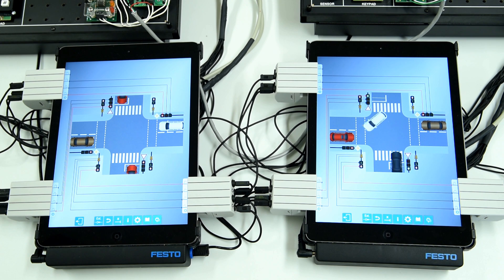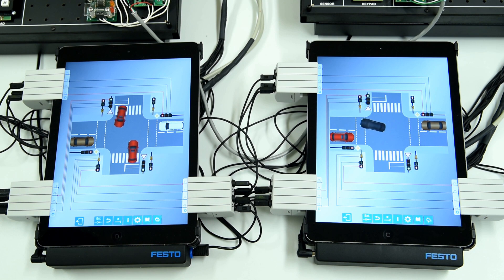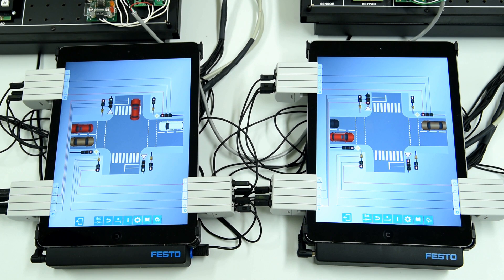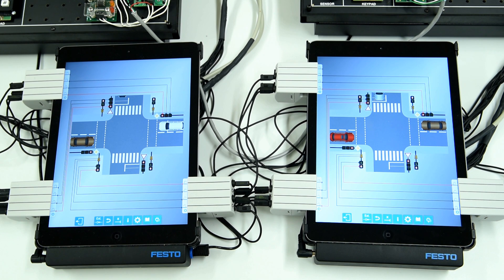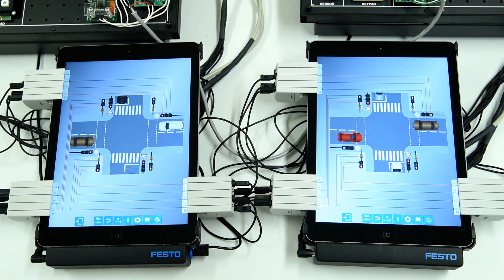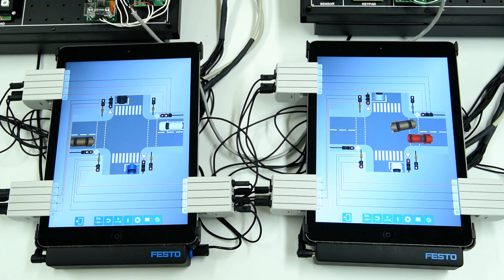And a pedestrian time message is exchanged between the controllers. Once both controller data bytes are set to ON, the pedestrians of both intersections get the light to cross. After a delay, the sequences are resumed, the data is reset, and traffic continues normally.